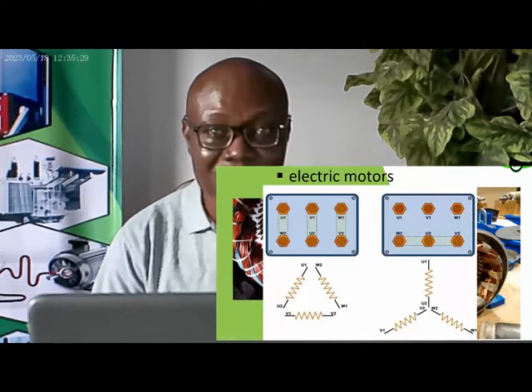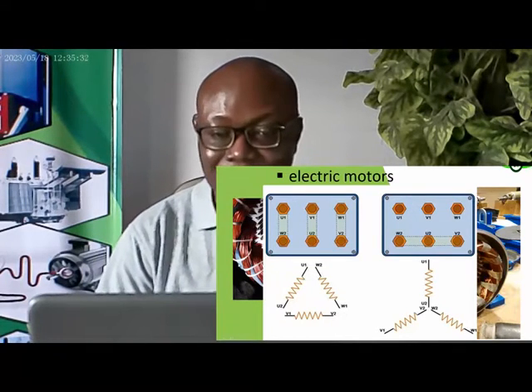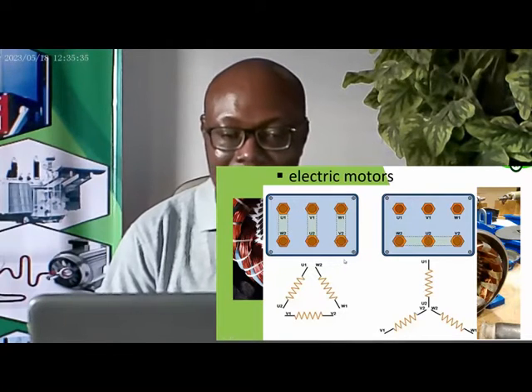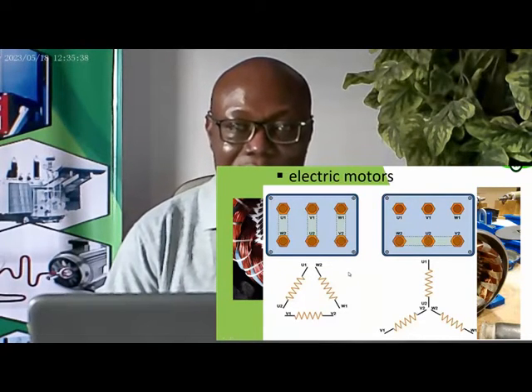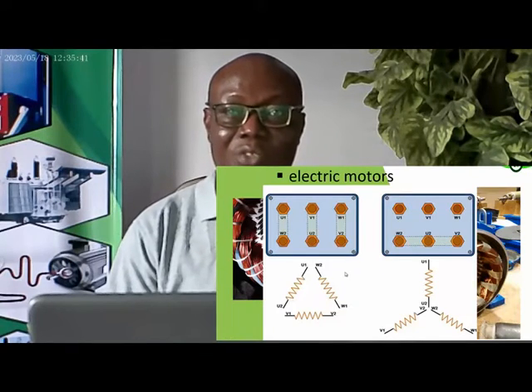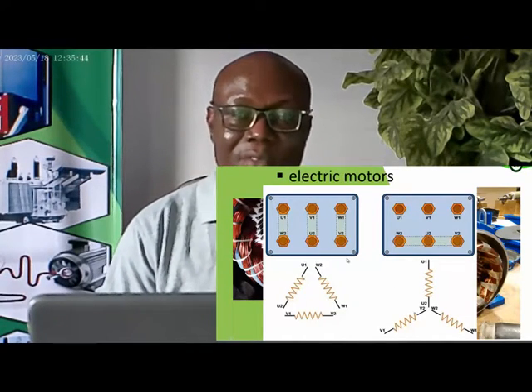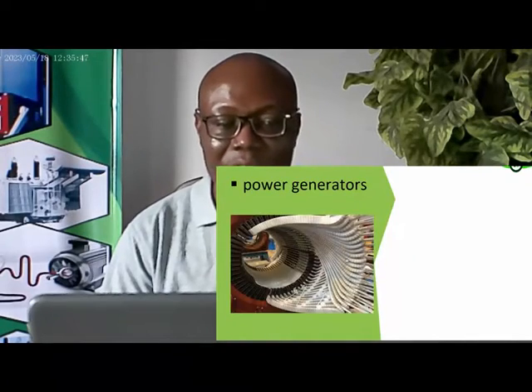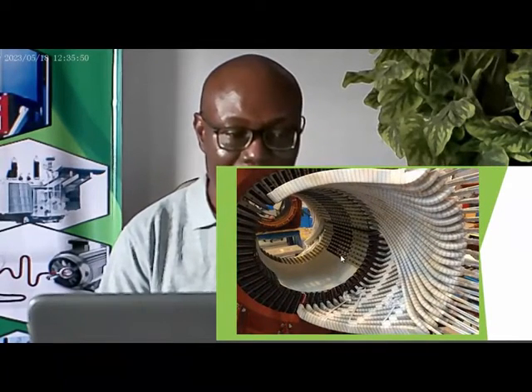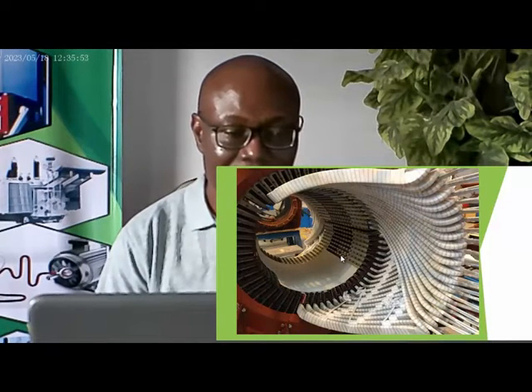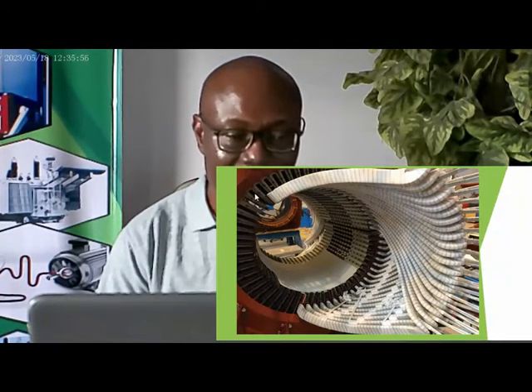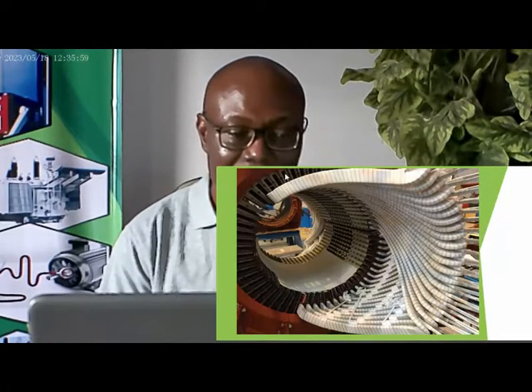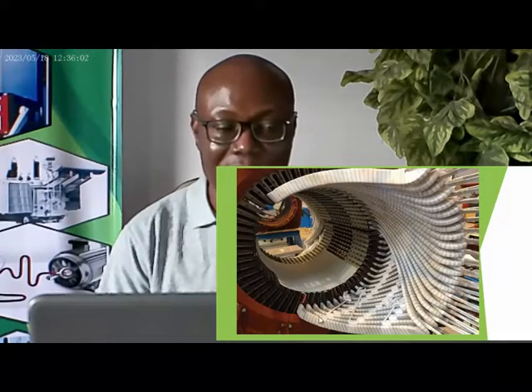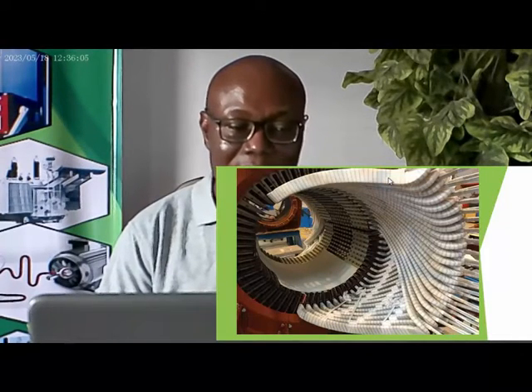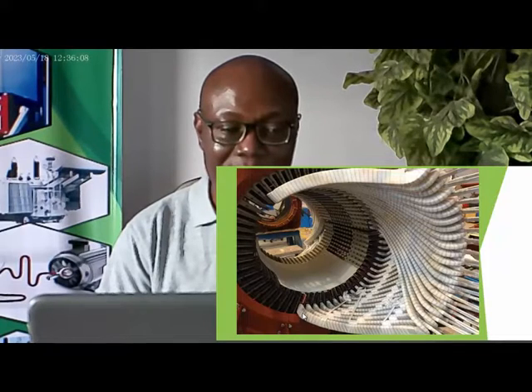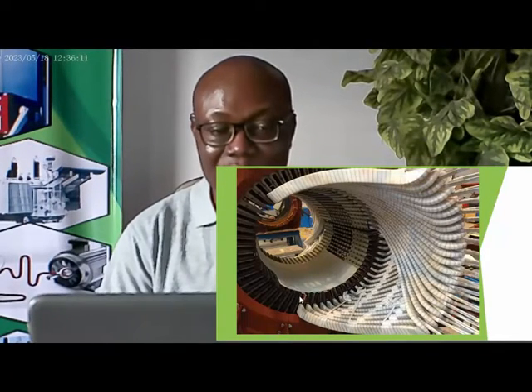Okay, since they don't have any business together, you expect very high insulation between the phases. The same thing applies to power generators too. Power generators are somewhat similar to electric motors. As you can see, the slots are insulated, and even the conductor itself is insulated. If you look at it critically, the conductor is insulated before it is placed into the winding, into the slot. The slot is also insulated.